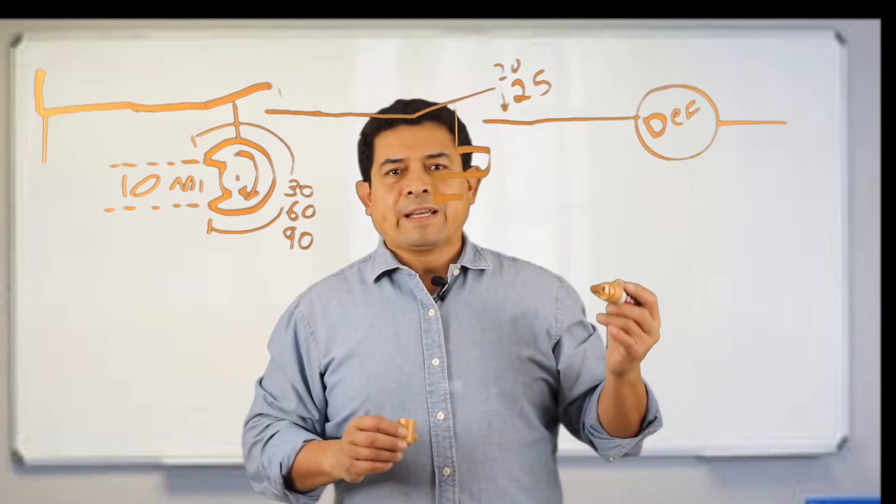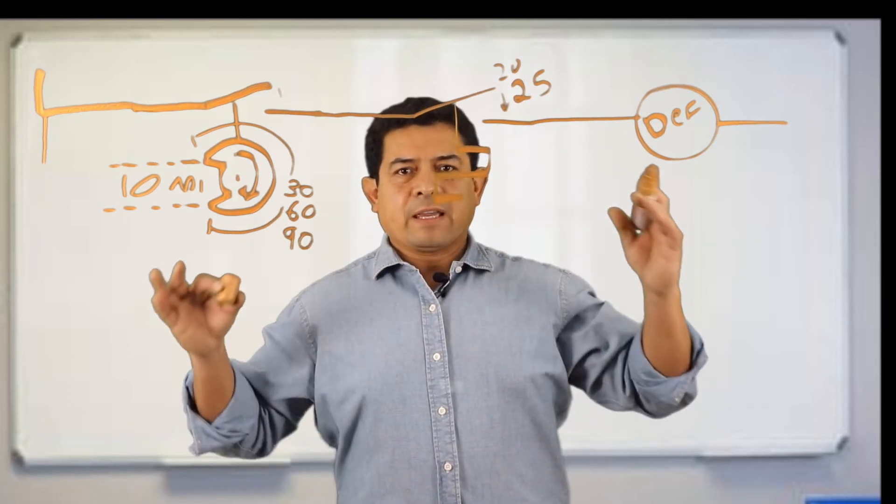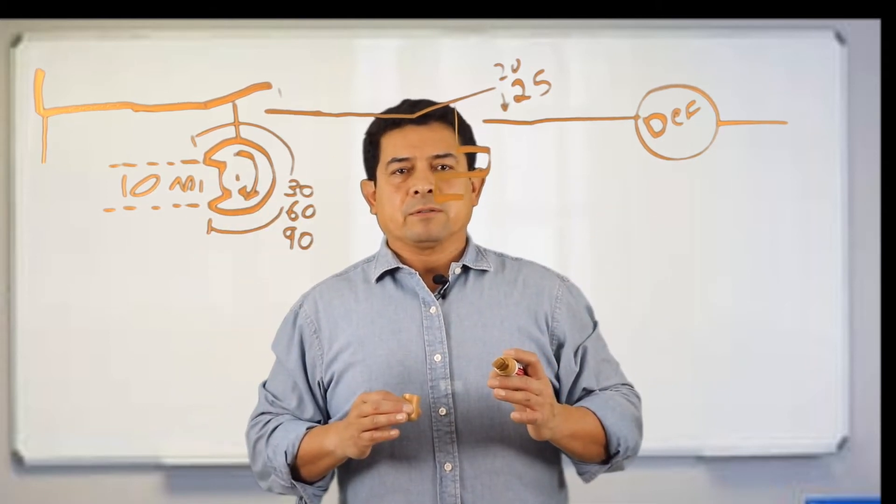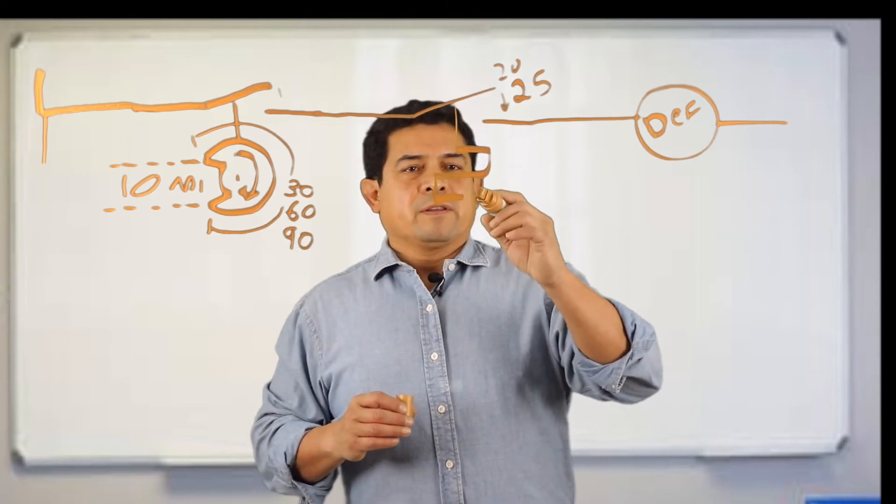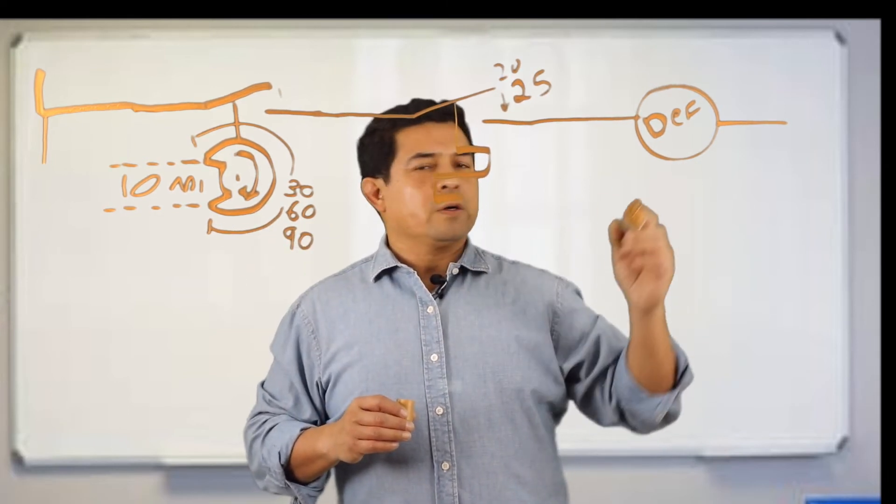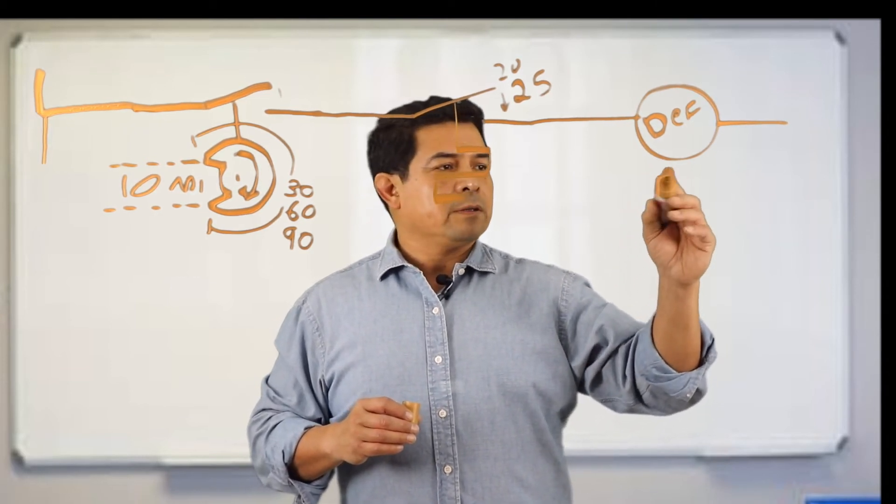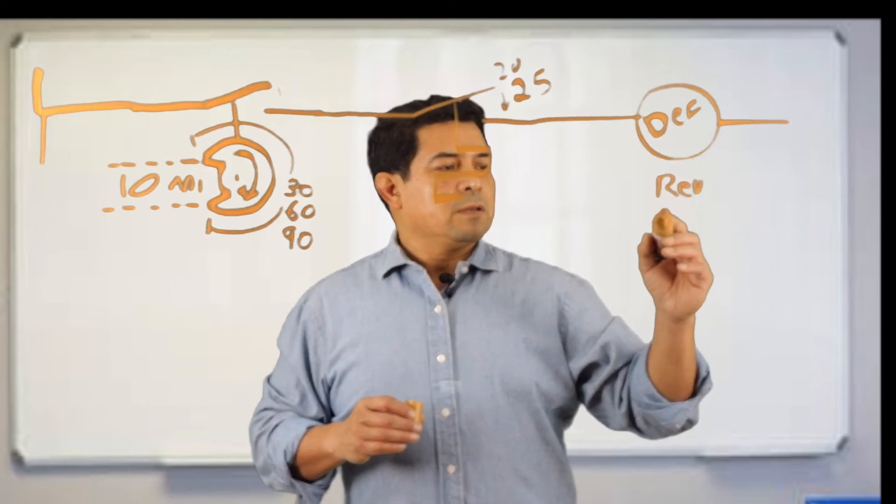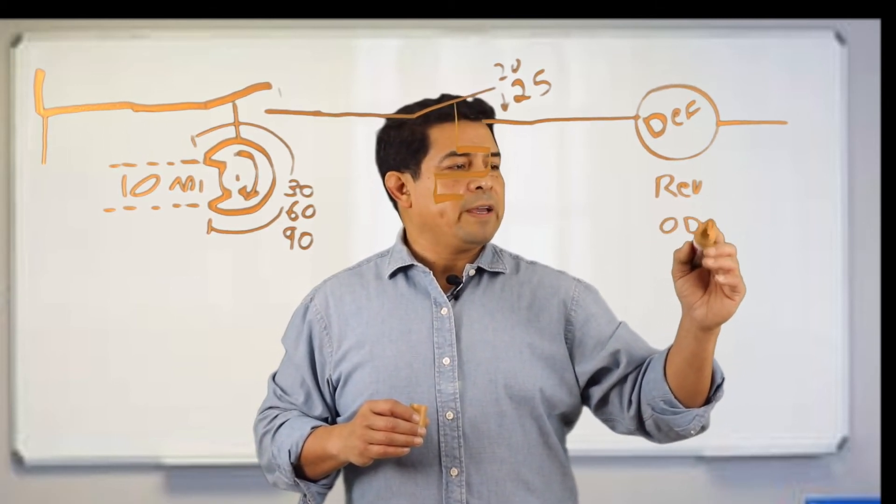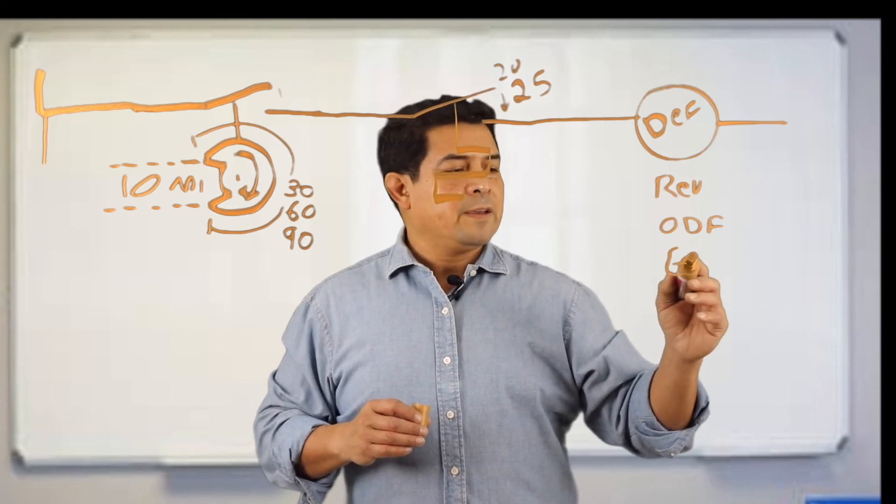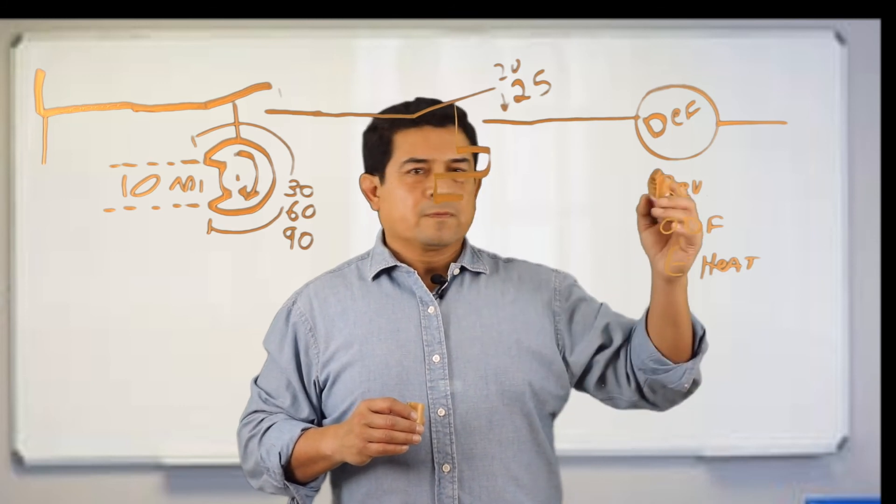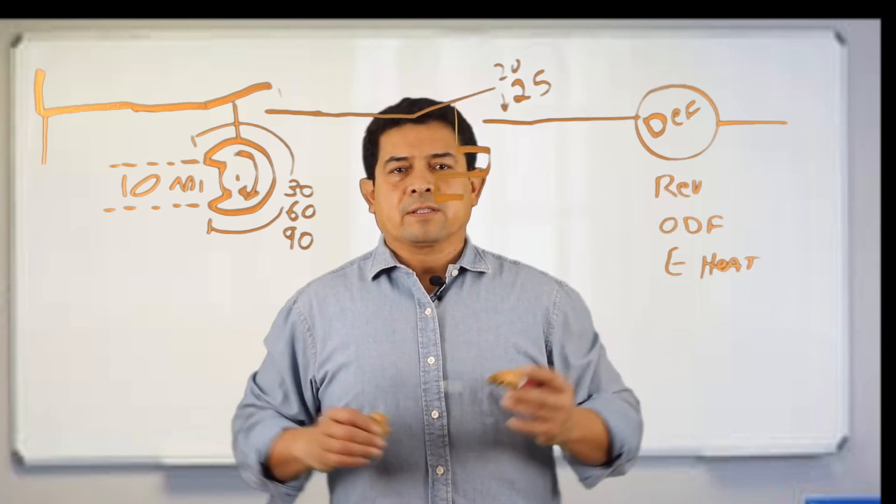We're going to try to keep things simple. Instead of thinking about the entire board, we're going to think about this right here, because this is what happens in defrost. The time has to happen, the temperature has to happen for it to go into defrost. The reversing valve shifts, the outdoor fan shuts off, and the electric heat comes on. This is your defrost cycle and how it happens.